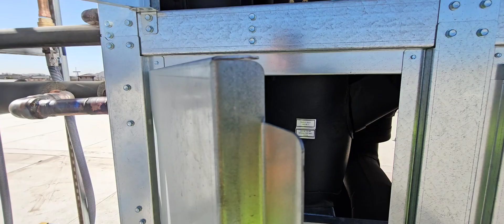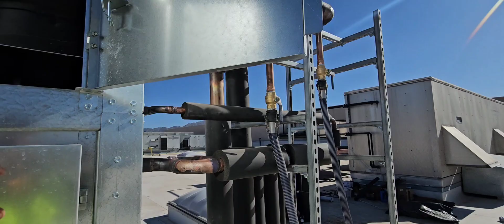So it's pretty simple, not a new technology by any means. I've seen this kind of system done a lot. It is new how they're doing it, though, like with the skid - it's like a retrofit skid almost. So it's like an existing DX rack, but they want to get some of the refrigerant off that rack. So they're gonna put in this glycol skid and take some of the refrigerant load off the rack and put it on the glycol skid.